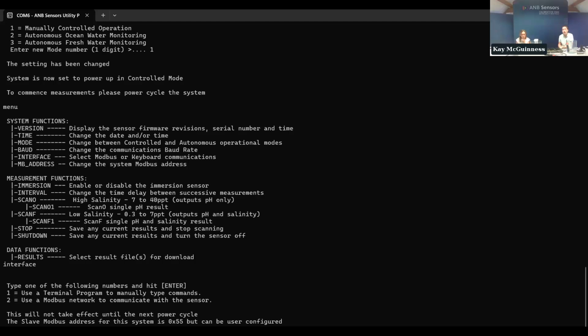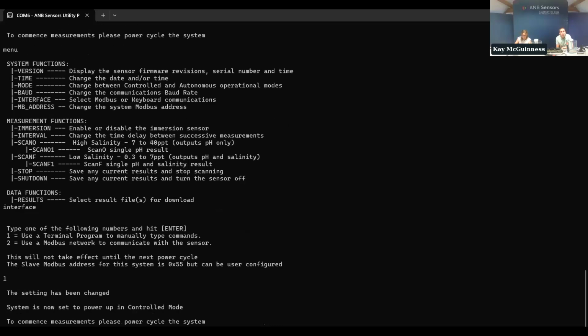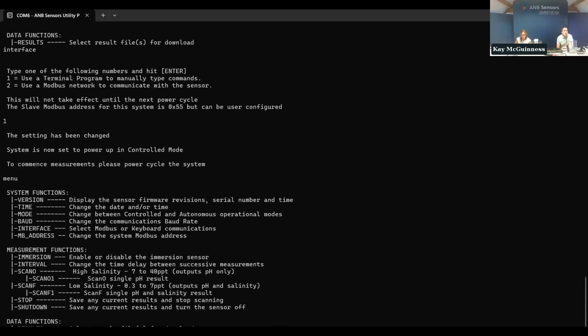It's worth saying, actually, if you're in Modbus and you want to get back to the keyboard communications, if you open utils, it automatically sends a command to get back to keyboard communications. Yeah. So this can be done on any terminal program. A #702 command sends the sensor back from Modbus into terminal mode, allowing you to reconfigure the sensor as you wish. Okay, and then moving on, in Modbus you can also change the Modbus address, can't you, from that? So all our sensors are either Modbus address 55 or the last 2 digits of the serial number. Obviously, if there's a conflict on a Modbus system, then you can change that address.